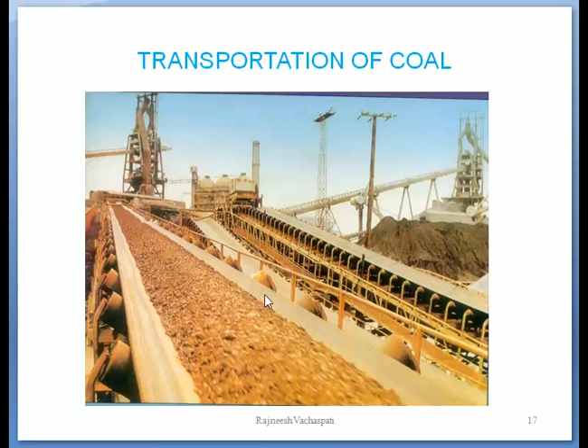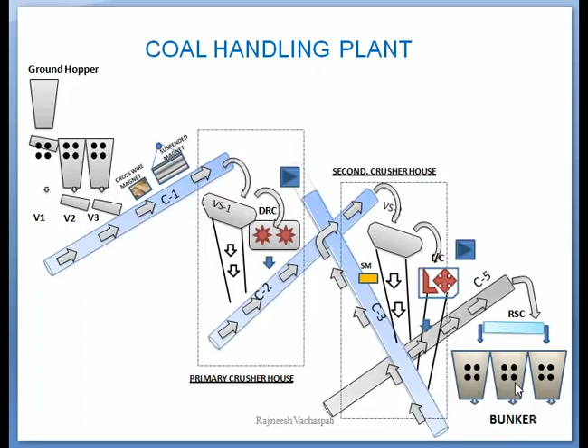The coal which is received generally varies in size. So after unloading it through conveyor belts, it comes to the primary crushing unit where the coal is crushed to a size of 125 mm. This 125 mm coal is then sent to the secondary crusher where its size becomes 25 mm, and this 25 mm coal is transported through conveyor belts to the main plant or to the milling plant where it is stored in the raw coal bunker. From this raw coal bunker through feeders, the coal goes to the pulverizers.